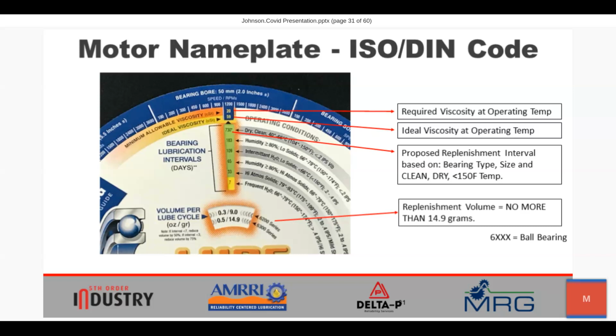Also, we see from the calculator, if it's a 6200 series bearing with a 50 millimeter bore, the volume is 9 grams or 0.3 ounces. If it's a 6300 series, which happens to be the case in this instance, we're looking at 14.9 grams or 0.5 ounces. And this is an instruction to us that we should put no more than that quantity of grease into the bearing cavity.